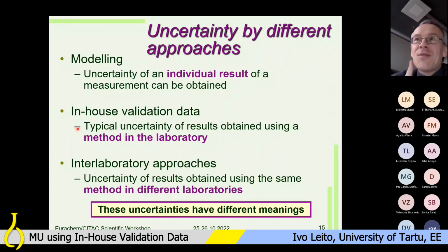And this, of course, again holds if your control samples for control charts, certified reference materials with which you determine recovery, etc., are similar to your everyday samples. If they are not, then you might not get the uncertainty that is really well applicable to your everyday sample.